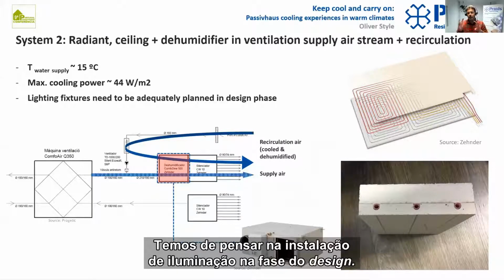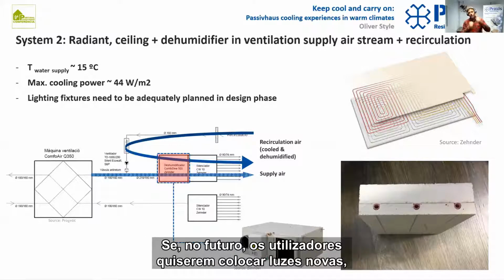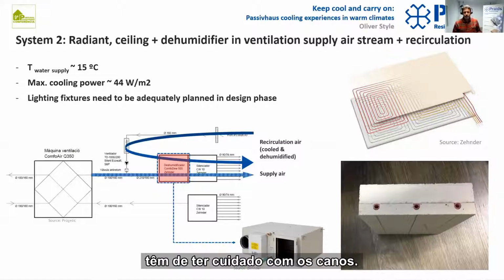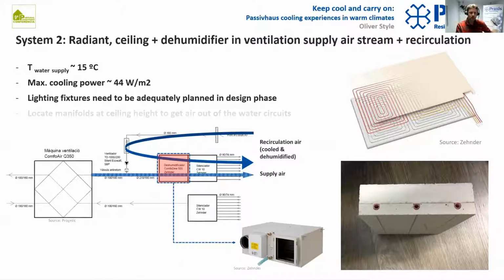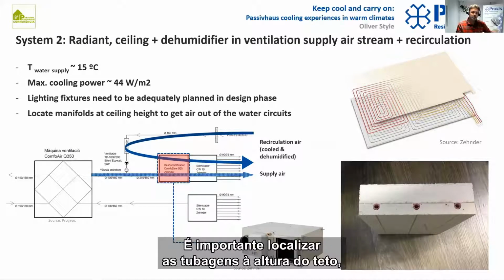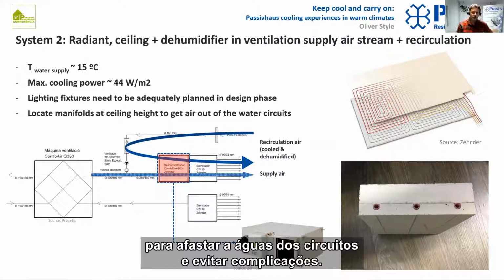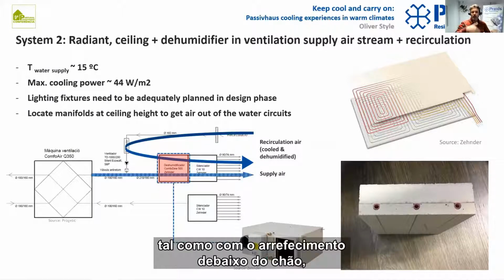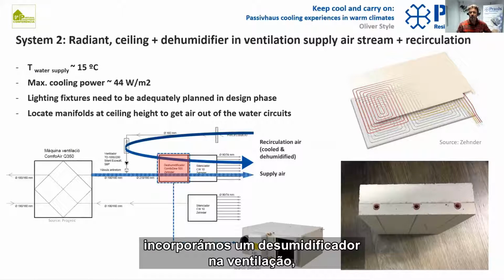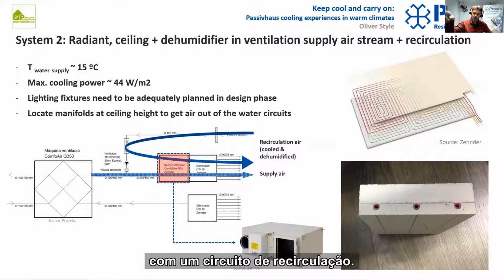We need to think about lighting fixtures in a design phase, and obviously users in the future, if they want to hang some new lights, they need to be careful not to drill through the pipes. Important to locate manifolds at ceiling height for commissioning to get air out of the circuits, which can otherwise be complicated. And what we did on this system was, again, as with the underfloor cooling, we incorporated a dehumidifier in the ventilation supply air stream with a recirculation loop.